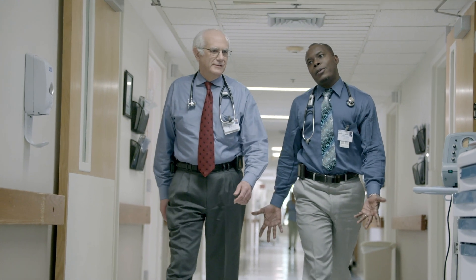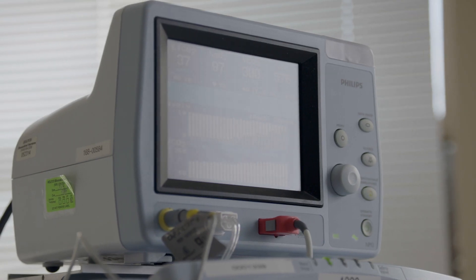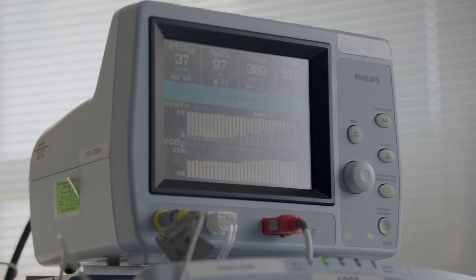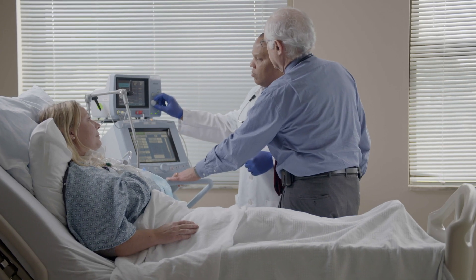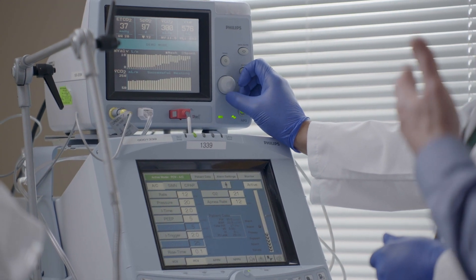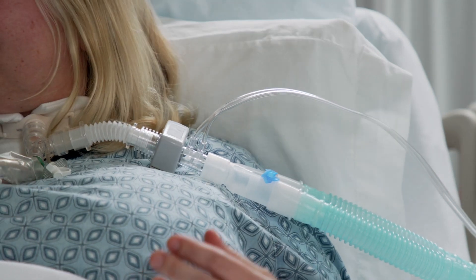I started looking at different ways to do things and whether there was something different we needed to do. I met a gentleman who was selling ventilators, and one day while we were talking, he told me about volumetric capnography. It measures the actual volume of exhaled carbon dioxide on every breath — like having a pulmonary function test on a screen where you're looking at the patient's lungs. It's non-invasive; it's a sensor that attaches to the ventilator tubing.